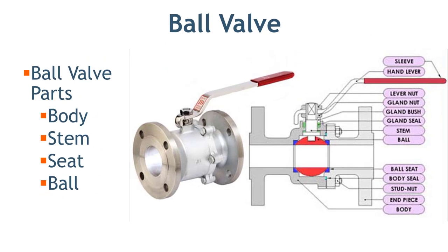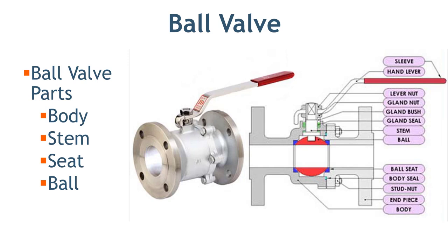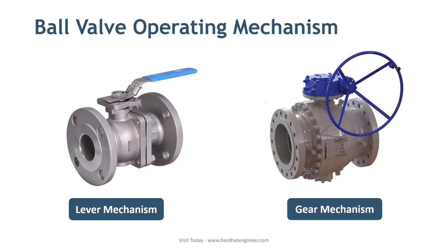The ball valve, like the one shown in this slide, is a positive shutoff valve. The operating mechanism of the ball valve is very simple. By just rotating the lever 90 degrees, which is connected with the ball-type disc through the stem, this valve can be fully closed or fully open. That is why it is called a quarter-turn rotary motion valve.